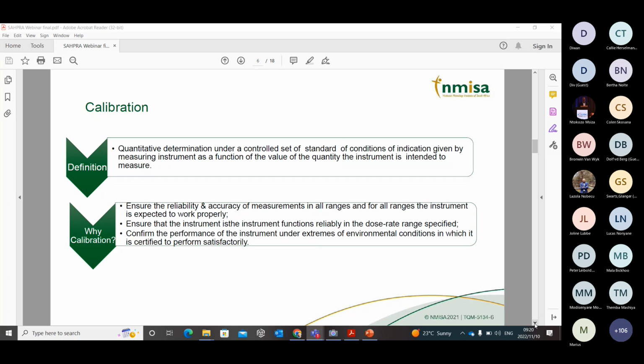So when I'm talking of the dose rate, I'm actually referring to us in the radiation community, because these can be in any range of measurement. But in the radiation community, we're speaking of dose rates, we're speaking of exposure rate, hence I use the words dose rate. And we also perform calibration to confirm the performance of the instrument under extreme environmental conditions in which it is certified to perform satisfactorily.